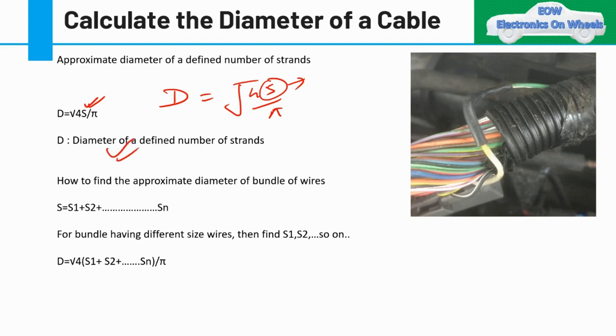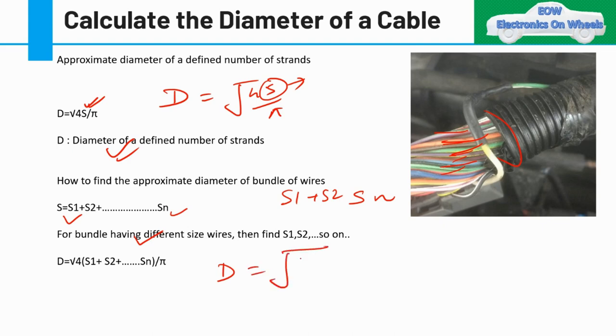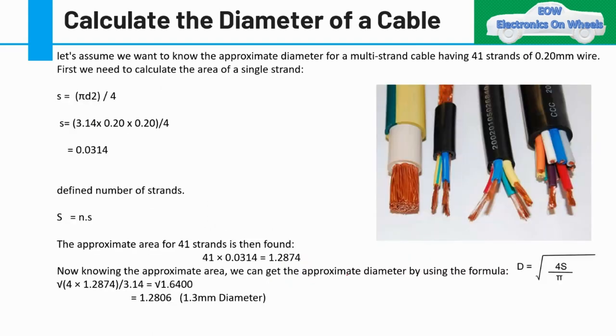If the bundle contains strands of different wire sizes — that is, different cross-sectional areas — you calculate S1, S2, S3 … Sn individually for each strand using the same π d² / 4 formula, then sum them. The bundle diameter becomes: D = √(4(S1 + S2 + … + Sn) / π). We'll now see a practical example of this.